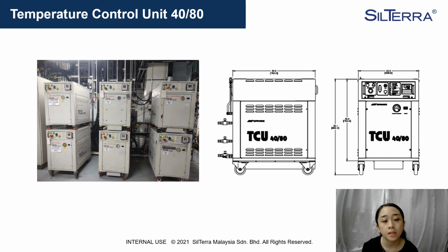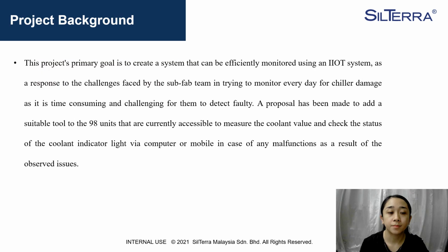With a tolerance of 1.0 degrees Celsius, the temperature control unit 4080 keeps supply coolant at a temperature of not less than 40 degrees Celsius and not more than 80 degrees Celsius. Okay, next we move to the project background.